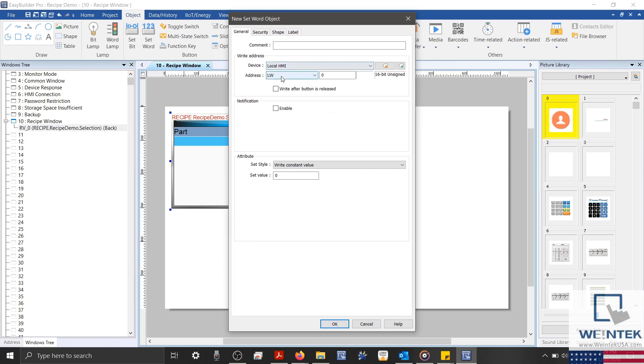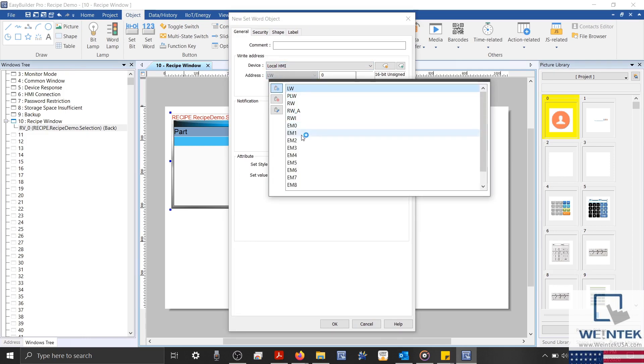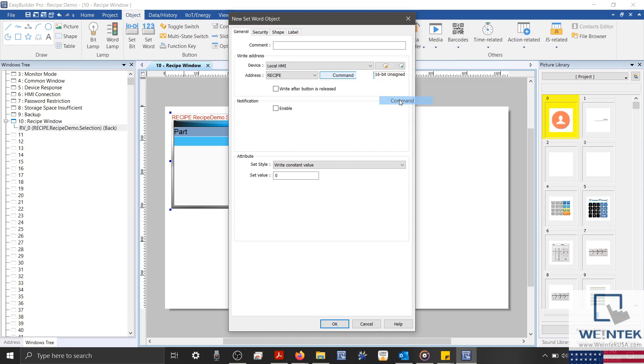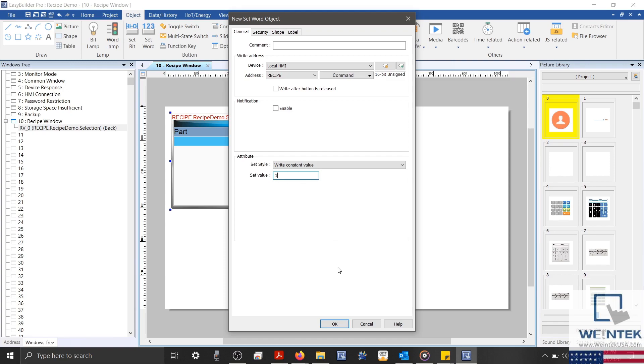I'll select Recipe from the drop-down list. And then in the secondary list, I'll select our Command Register. Now, in previous versions of EasyBuilder Pro, we would normally define a 1 within our Set Value box to send a command to add a new recipe. And we could continue creating our objects in this way until we've defined all of the commands that we need for our recipe to function.